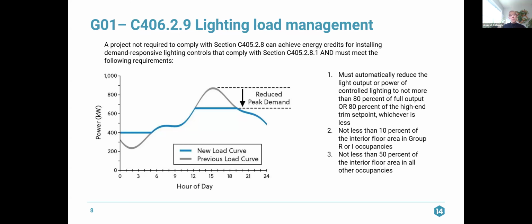So if you remember those high-end trim controls that we were talking about on Tuesday, we had to set the maximum output of the total fixture to 85%. And now we have this compliance pathway for the load management credit, where in an instance of a peak demand event, the maximum capacity would be 80% of that 85% that we were allowing. So our high-end trim set point is 85% of the lighting fixture's total output, and we reduce that to 80% of the 85%, not just to 80%, which I guess I probably should have calculated out.